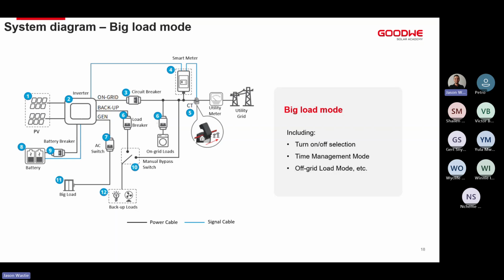We can also do it based on battery SOC settings. So when my batteries are at 100%, allow me to discharge up to my backup loads and to my secondary backup loads, so my generator port loads. And when the batteries reach a certain SOC, let's call it 50%, turn off all the loads on the generator port and allow only my actual backup loads to run. That way you can run, quote unquote, your entire house when the batteries are full, and when it reaches 50% or whatever it is, turn off everything and only run my core essential loads.